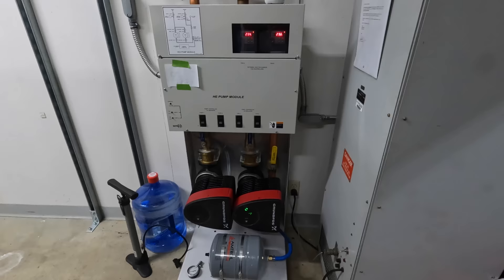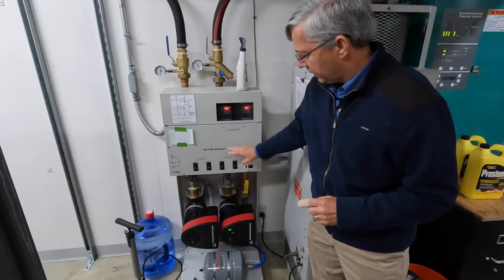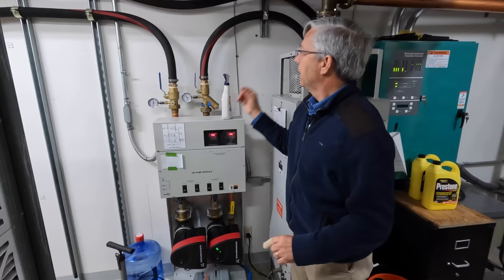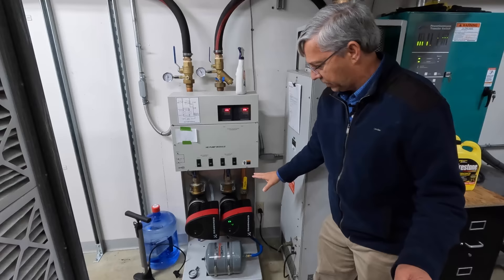In this particular transmitter we have a rare sighting of a water-cooled FM transmitter. TV guys have done this for decades, but it's kind of new on the FM side. You've got two pumps — it circulates out and most of the heat gets dissipated to a fan system outside. The water comes back in, goes through the transmitter, comes back out, and gets pumped through the units out there. We keep an eye on the intake and output pressure, and either pump can make the system work.